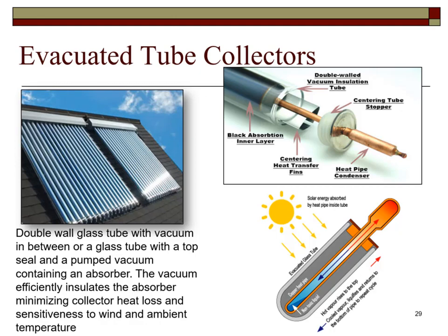This shows the construction details of the evacuated tube. The vacuum inside the evacuated tube collector greatly increases the amount of thermal energy focused into the pipes. Although they look easily breakable, they are rather durable and capable of withstanding extreme weather conditions. Most evacuated tubes are not made in the United States and therefore not constructed with a high degree of quality assurance or consistency. If you are going to purchase these, be prepared to do your homework to find not only the best deal, but the best quality.